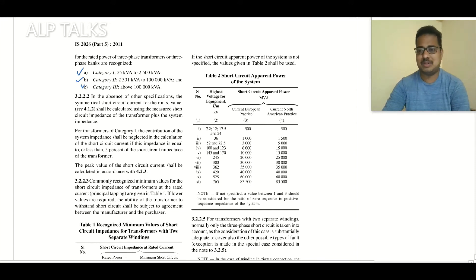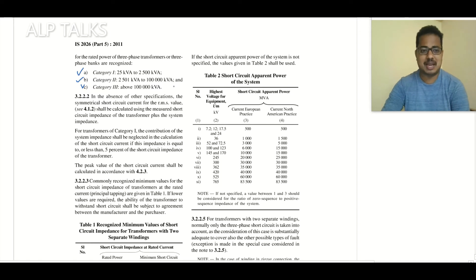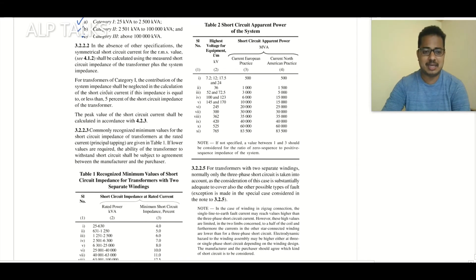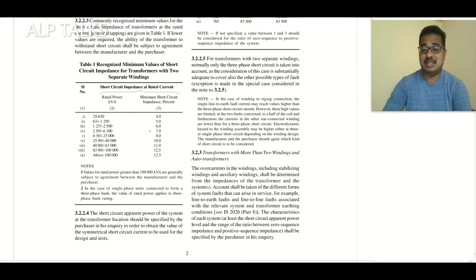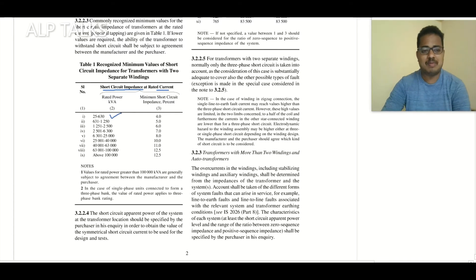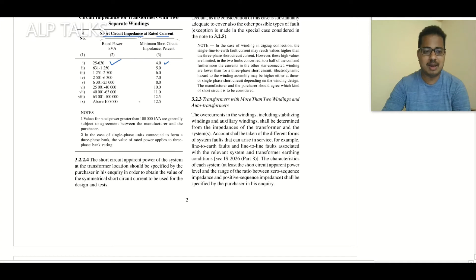Category 1 is 25 kVA to 2500 kVA, Category 2 is 2501 kVA to 100 MVA, and Category 3 is above 100 MVA. This standard also proposes the minimum impedance required for each kVA rating. For example, from 25 kVA to 630 kVA, 4% is the minimum recommended impedance based on short circuit current. From 1250 to 2500 kVA it is 6%.